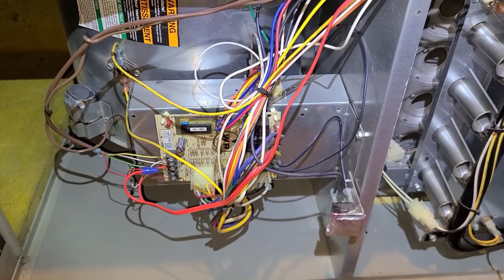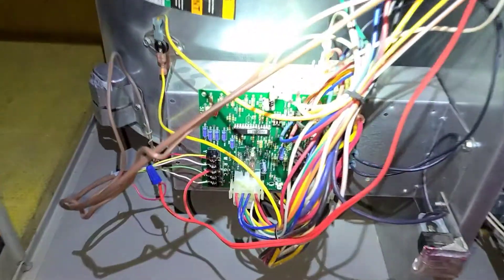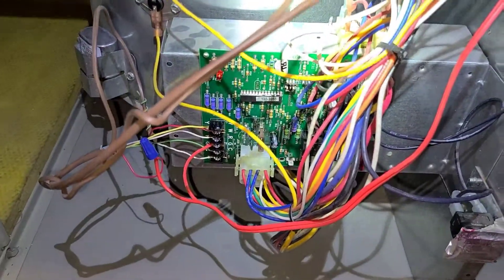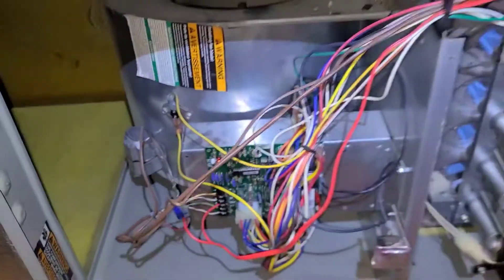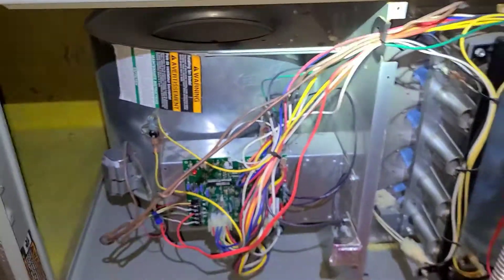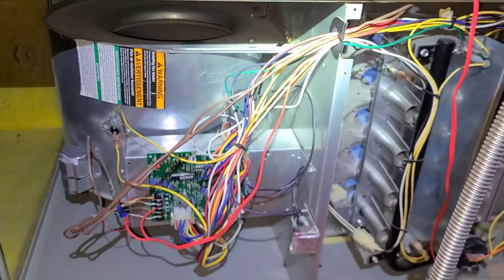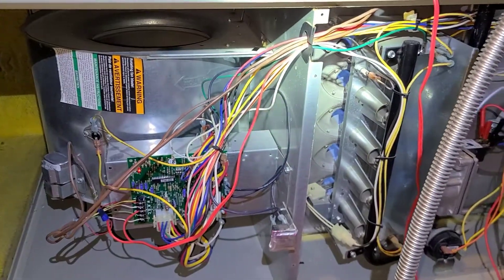Installed the new control board. Here's the old one. Unit is heating now. Was not heating before due to lack of 24 volts getting energized at the gas valve.